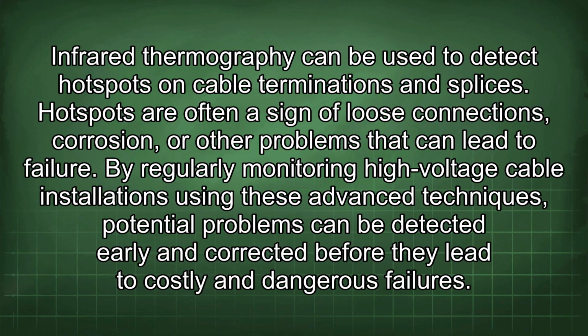Infrared thermography can be used to detect hotspots on cable terminations and splices. Hotspots are often a sign of loose connections, corrosion, or other problems that can lead to failure. By regularly monitoring high-voltage cable installations using these advanced techniques, potential problems can be detected early and corrected before they lead to costly and dangerous failures.